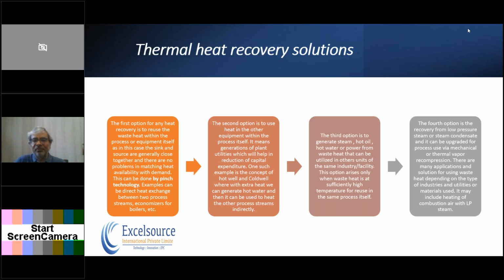We have to select the equipment in a way that it can handle the higher temperature within the absorption tower, and that heat is available, which can produce low pressure steam or pressurized hot water up to 3 bar, or maybe up to 160 degrees Celsius. And this high temperature water can be taken for operation of the VAM or any other application, where we can get useful output from the waste heat.